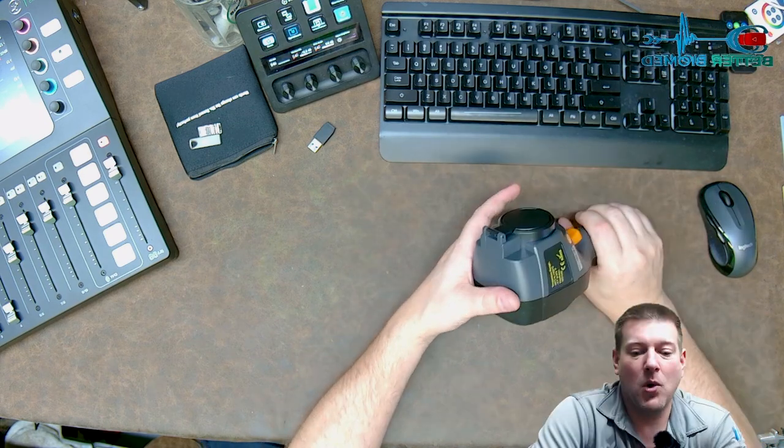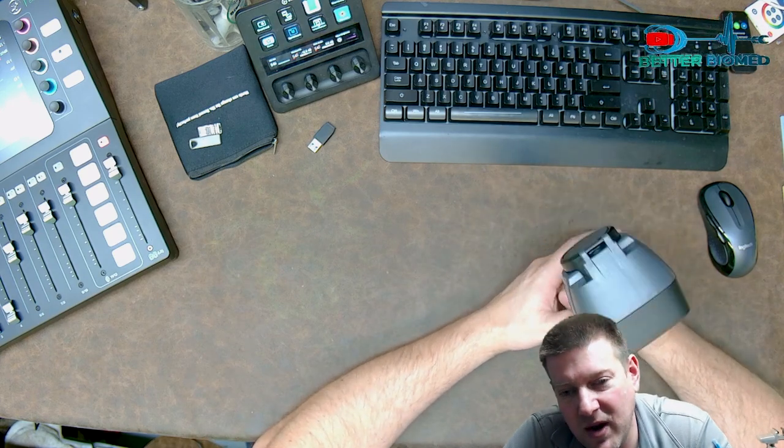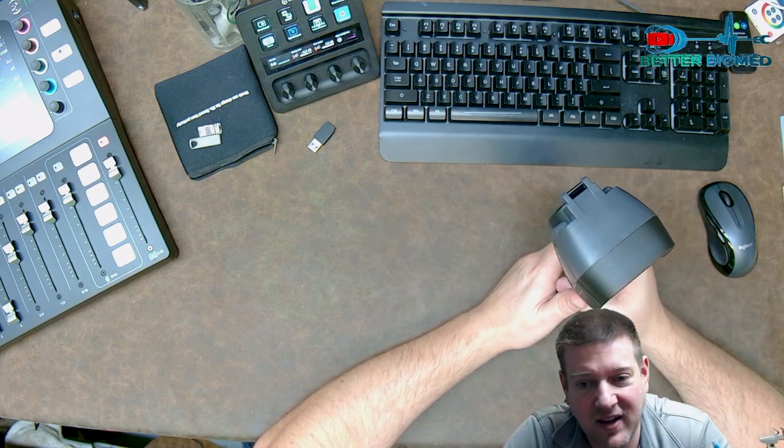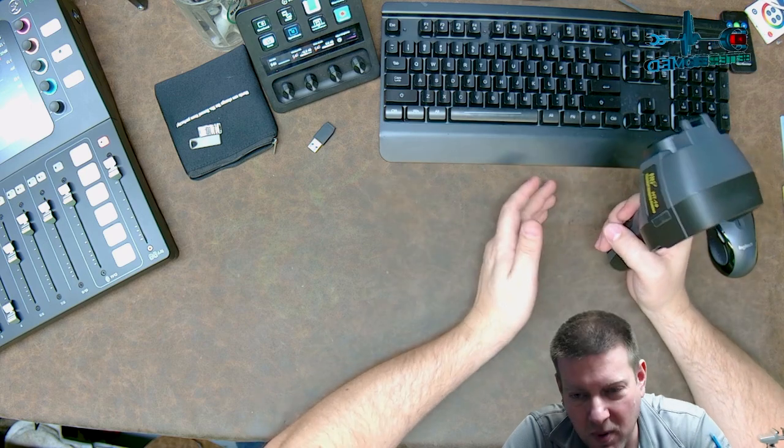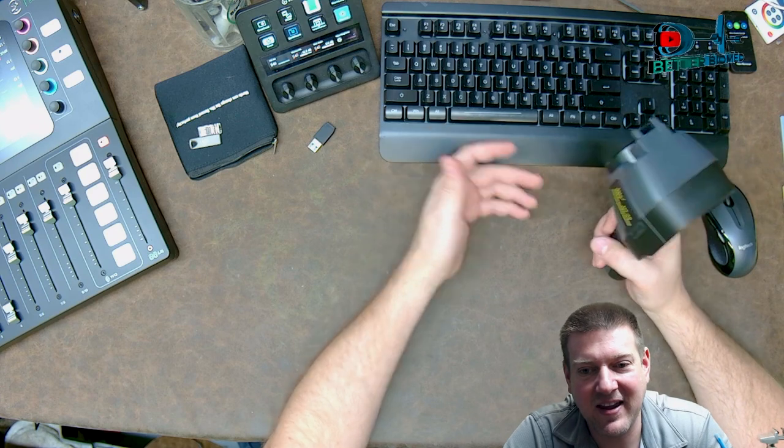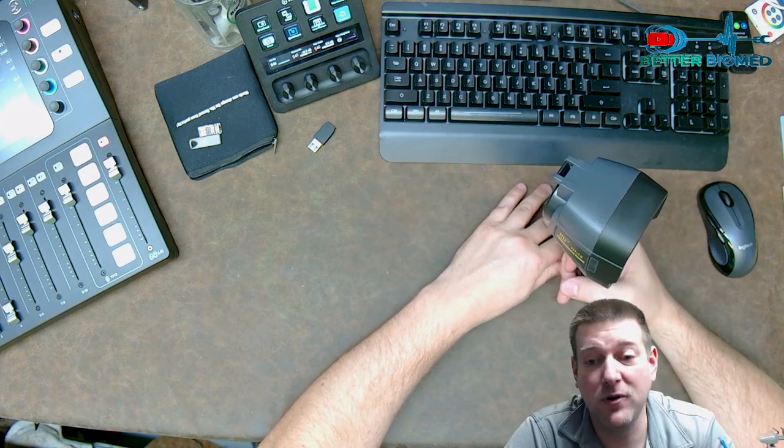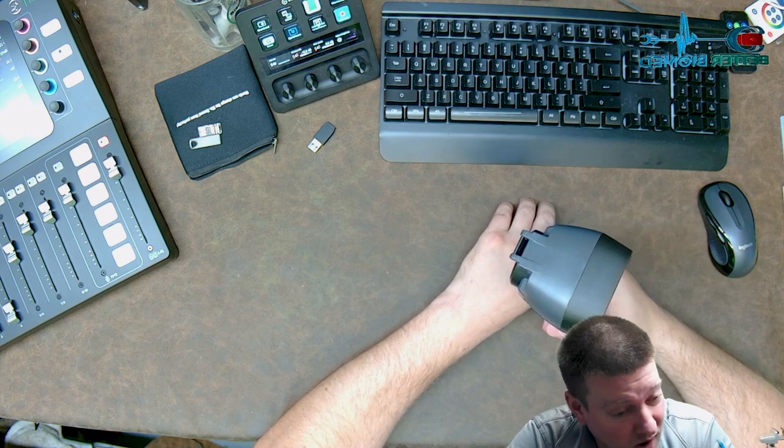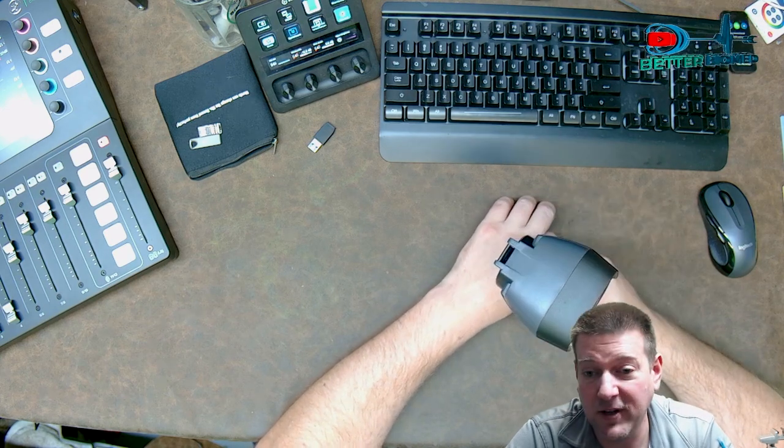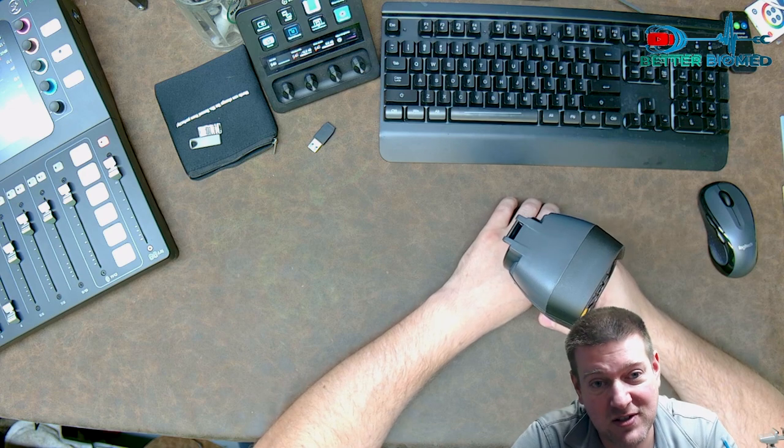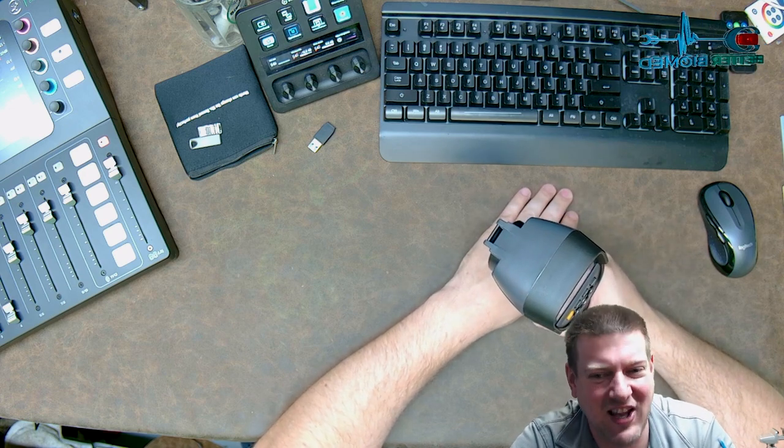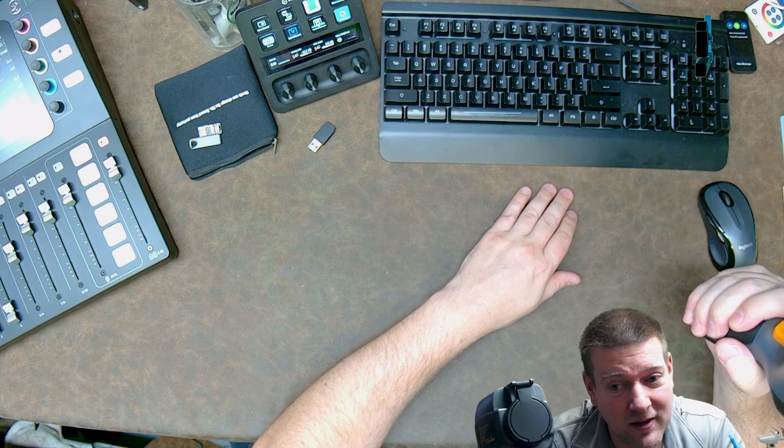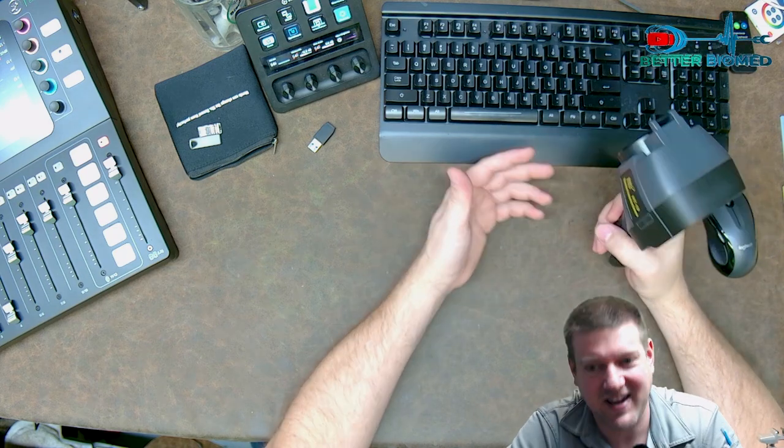So you got to watch yourself when you go to buy a thermal camera, but there is a lot of new technology out there. And what used to be a prohibitive technology, like FLIR was one of the main companies that used to do it. And it was thousands of dollars for those cameras. Now you can find good cameras for a few hundred bucks. They can do most anything you want them to do. So even if you only use it once or twice per year, this guy right here, if you use it correctly, can diagnose so many problems for you so much quicker, which is the key. I can't tell you how many times I've had faulty fuse panels. I've had motors that got too hot. I've had faulty cooling fans. I've had central monitoring stations that were completely jam packed full of lint. I would have seen it if I had one of these and it only takes seconds.